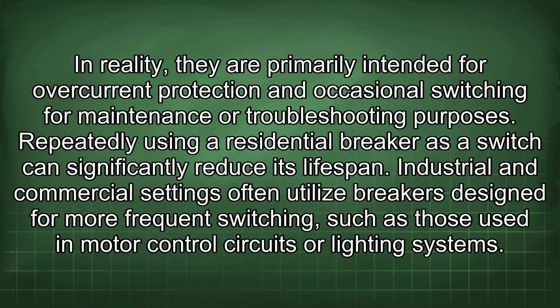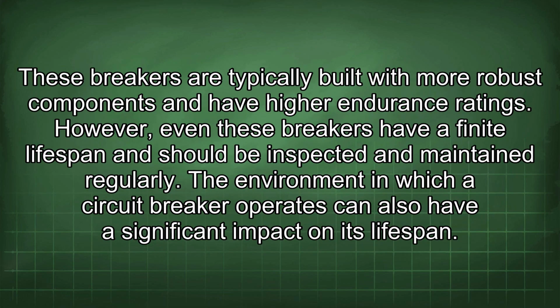Industrial and commercial settings often utilize breakers designed for more frequent switching, such as those used in motor control circuits or lighting systems. These breakers are typically built with more robust components and have higher endurance ratings. However, even these breakers have a finite lifespan and should be inspected and maintained regularly. The environment in which a circuit breaker operates can also have a significant impact on its lifespan.